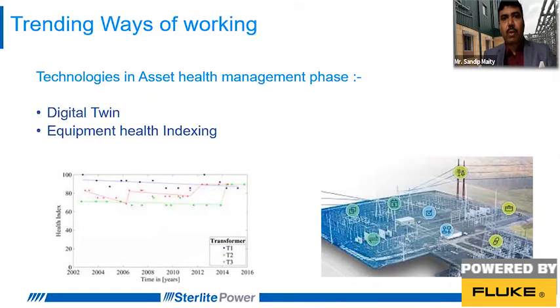Like Mr. Bogan was talking about PD level or thermal imaging, all that data. Once it's fed to the model, it gives indications of what life to expect from a transformer or circuit breaker, and if there's any change in behavior or properties in between, we can observe it from this digital twin model and plan maintenance accordingly. That's how we increase asset uptime, which is essential today to have 24/7 power.